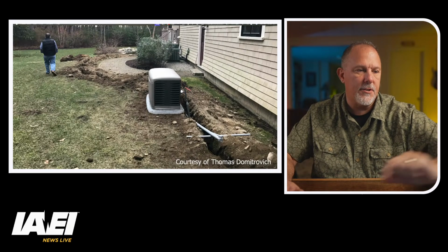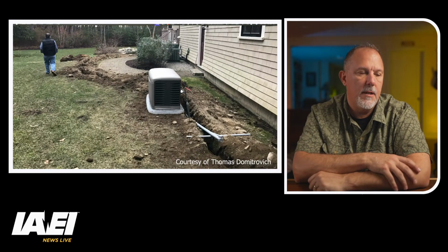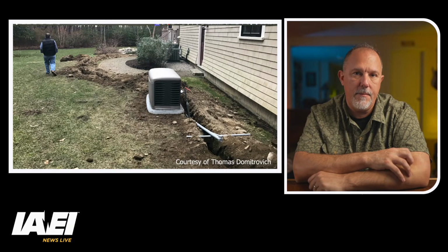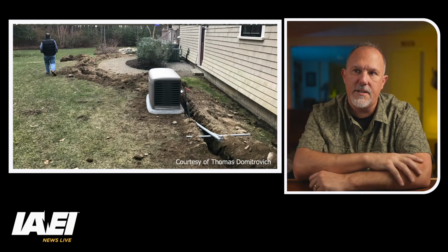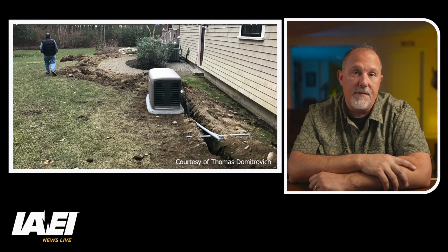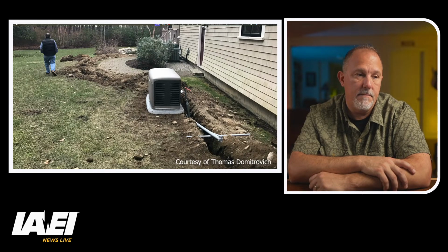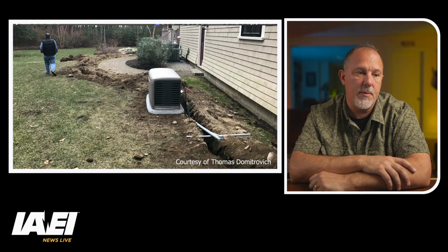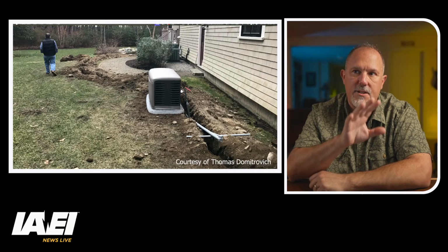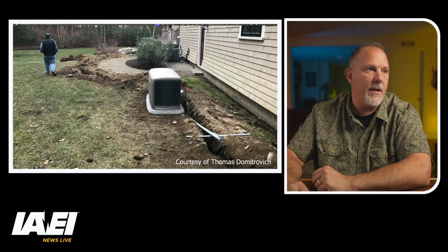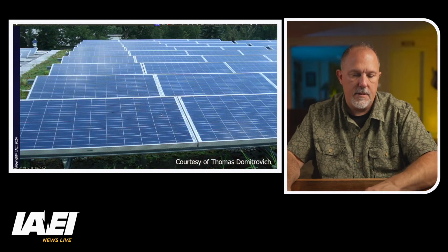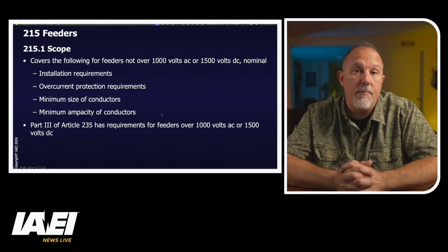Power source output conductors. Power source output conductors is a challenging term in many different ways, because the conductors coming off of this power source here are feeders. They are not to be used as power source output conductors, because it says the conductors between power production equipment and the service or other premises wiring. It's a term that presents a challenge for us, but we've got to move beyond that and move into feeders.